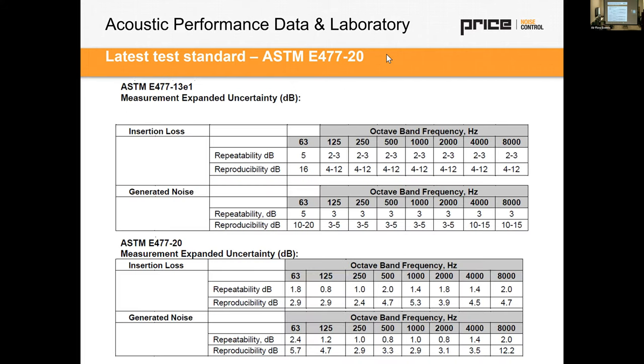And the reason for that is that the performance variations and ranges of what is deemed acceptable have changed. This table is a little bit busy here, so we'll try and simplify it. But at the top is the last version of the standard. It was ASTM E477-13, 2013. It's about 10 years ago. And what happened in that standard is there was a very wide range of acceptability on what we call repeatability and reproducibility. It's a bit of a tongue twister. Reproducibility, repeatability. Anyways, get your kids to say that five times fast.